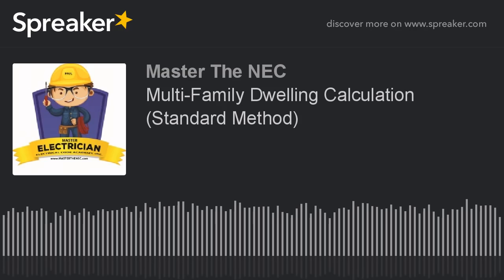So that's the value you're going to write underneath the 60,750 that you just wrote for the water heater. So you're going to write 36,000. Now, we have a neutral load here because we said that this dryer was a 120/240 volt dryer. So what do we do with the neutral load?